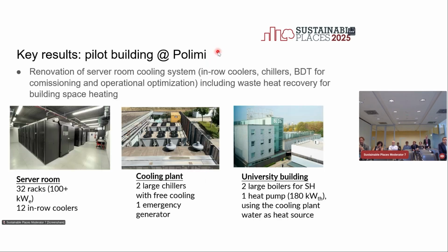For testing, as I said, we will do it at the Bovisa campus. This is our server room with 32 racks. Last year we were using computers that were not super new, with 100 kilowatts of electric power. Now we are replacing it with much newer computers with much higher power density, reaching 200 kilowatts of power that we have to dissipate. The maximum capacity of the cooling system here is 300 kilowatts, and we will reach it very soon.